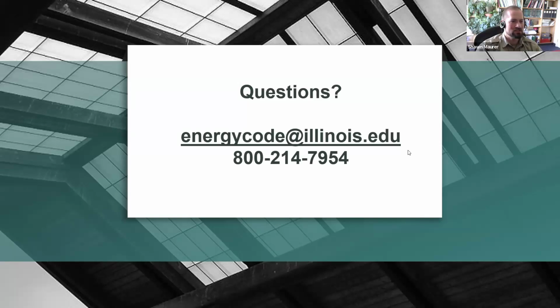Question about the open plan offices. The 300 square foot is the definition separation between other types of offices and an open plan office. The maximum controlled area allowed for an occupancy sensor is 600 square foot. So it's not zoning between 300 and 600 square foot for those offices. An open plan office is defined as an office area with an open plan without dividing walls that's 300 square feet or larger, and then individual control zones within that can be a maximum of 600 square feet. Hopefully that makes sense.